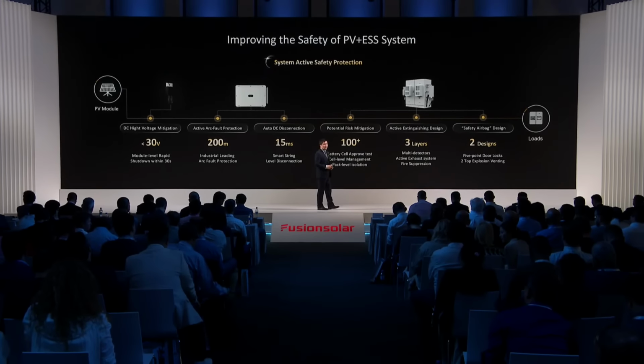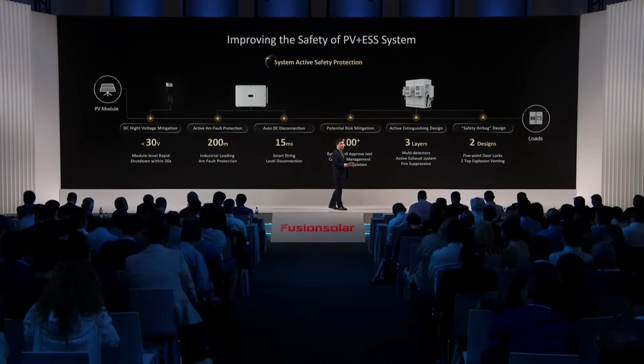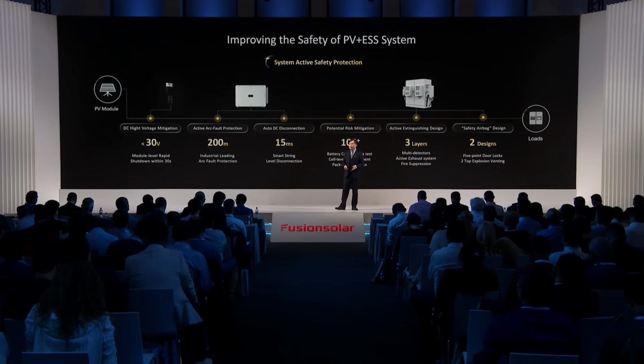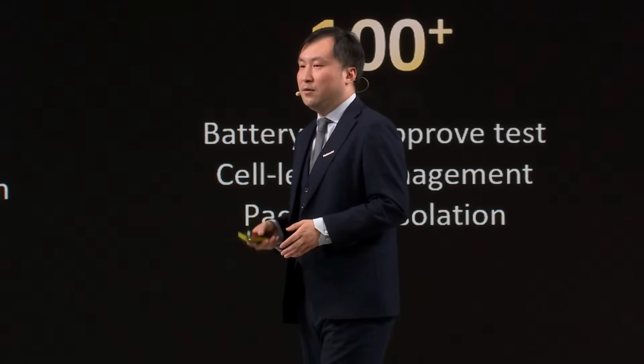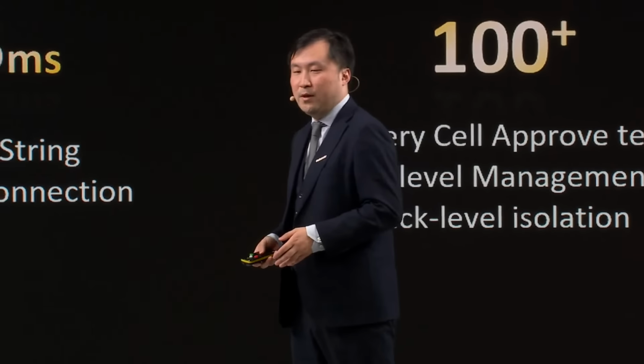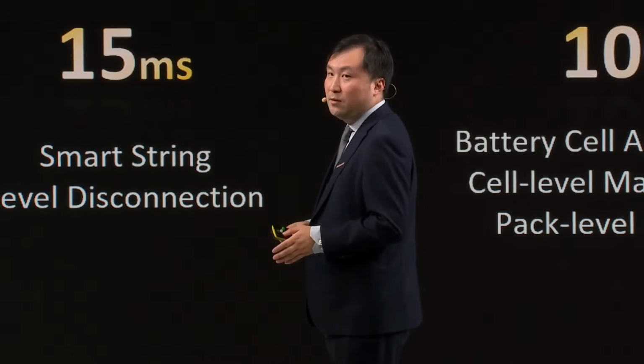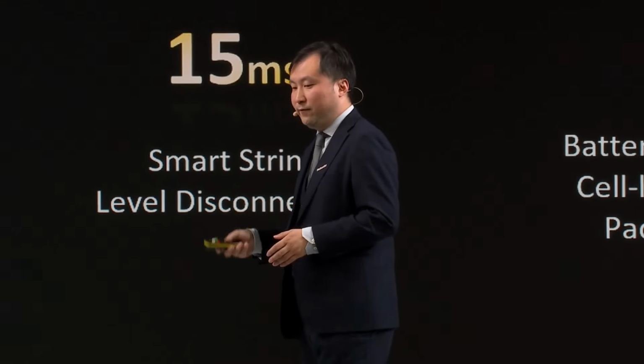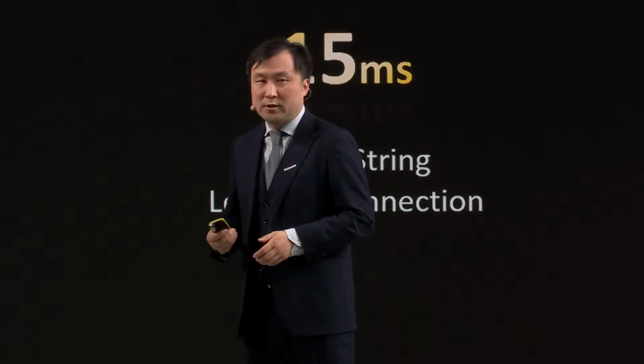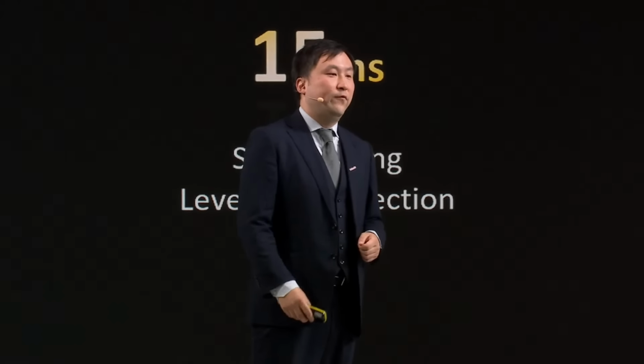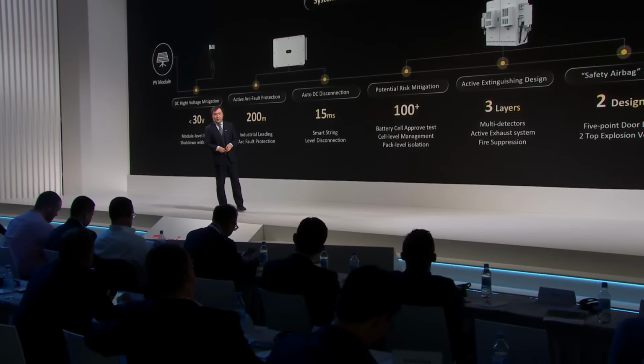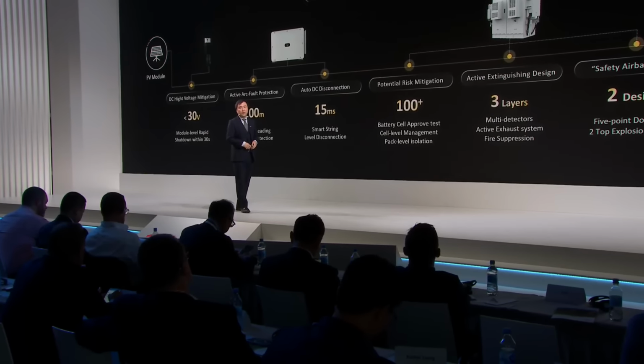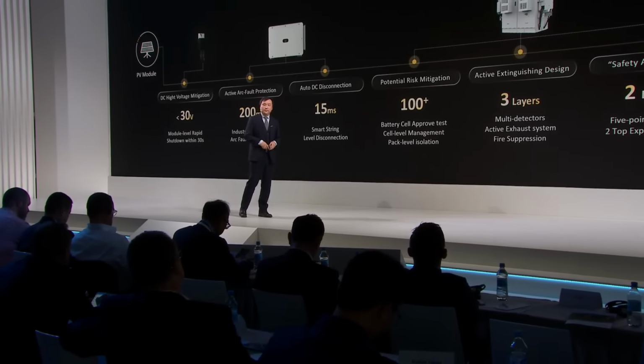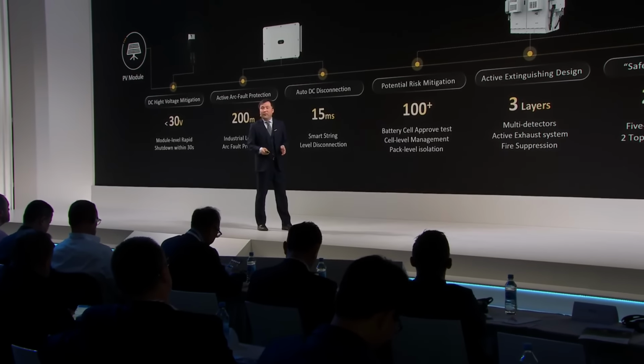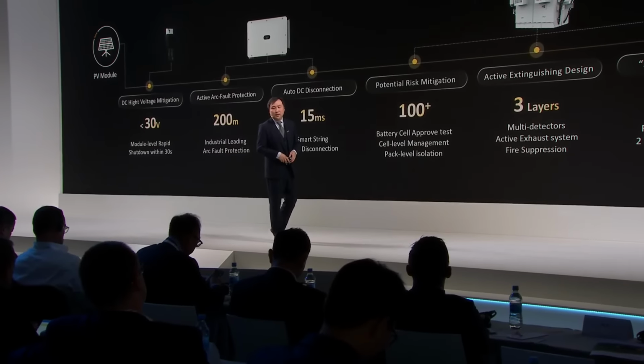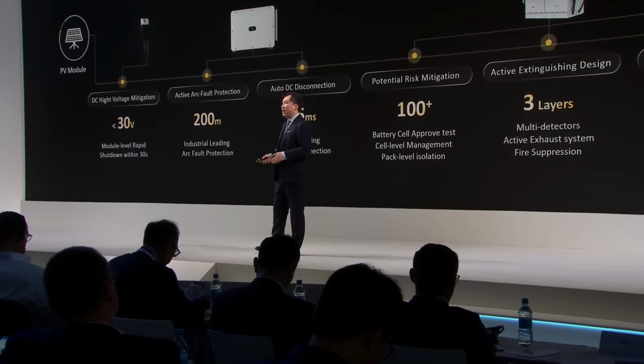In PV installation, the core challenge is always from the DC side. First, we have applied our unique smart string disconnection technology in the inverter, which can disconnect the DC within 15 milliseconds to ensure device safety when a DC fault occurs. Second, we further enhanced the AFCI capability to cover DC sub-areas with a radius of more than 200 meters, disconnecting the system within 0.5 seconds and eliminating the hidden risk of fires caused by arcs.